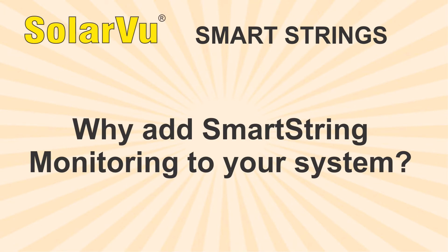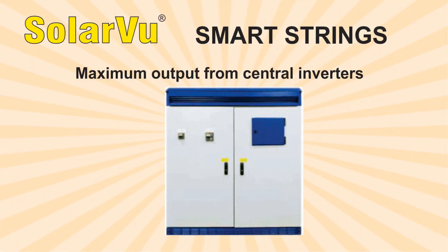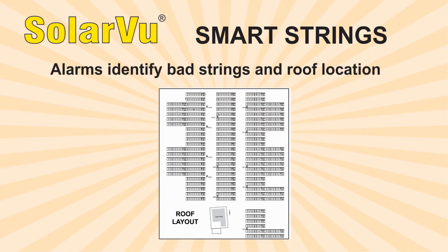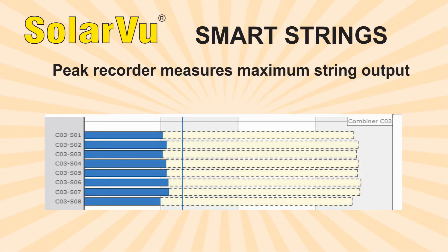Why add the Smart Strings option to your SolarVu system? Smart String monitoring is recommended for large 50 to 500 kilowatt systems with central inverters to ensure they are always operating at maximum output. Without it, a low output string could go undetected for a long time resulting in significant lost revenue. SolarVu checks every string under all irradiance conditions and sends an alarm if one string is significantly below the others. Operations and maintenance staff can download a roof layout to quickly locate and repair a defective string. Compare all strings to each other to determine if any are underperforming due to aging, soiling or snow coverage.